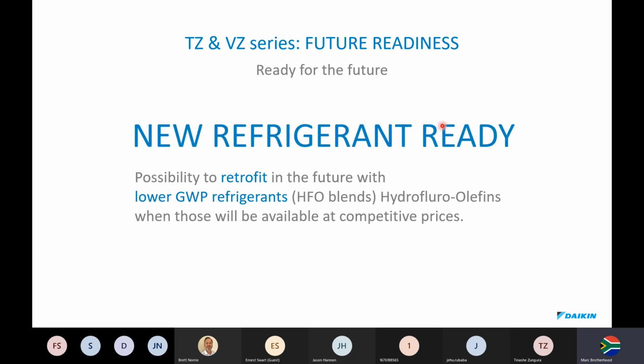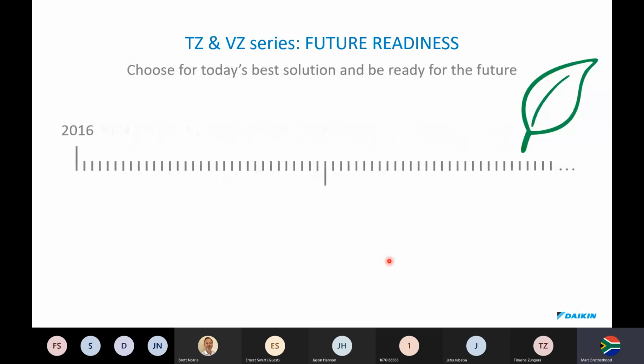I mentioned to you earlier on about the new refrigerants. So the good thing is, if and when they do decide to phase out 134A, it's possible to retrofit the existing systems with lower global warming potential refrigerants, which we call HFOs, which are hydrofluoroolefins, and those are also going to be available at competitive prices.